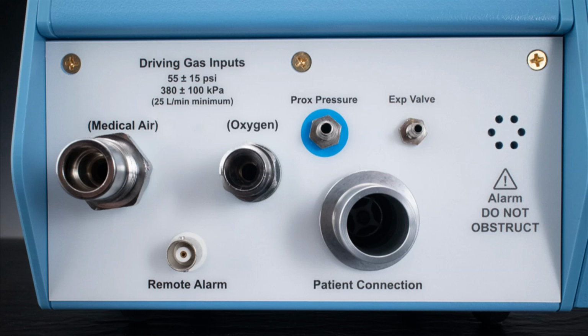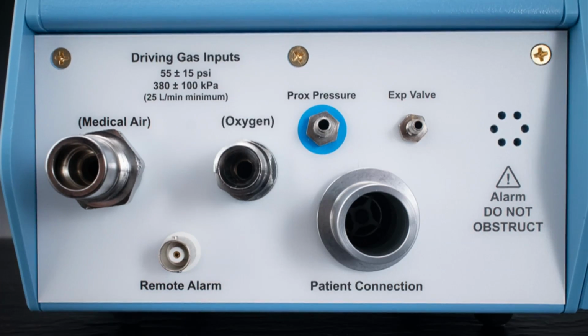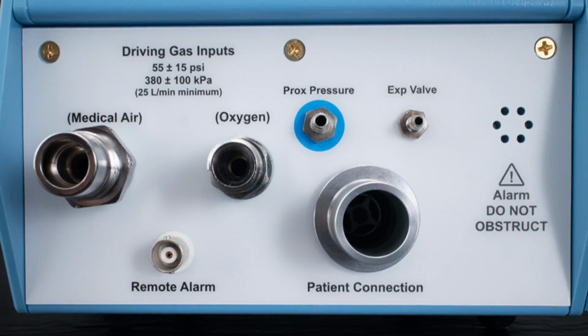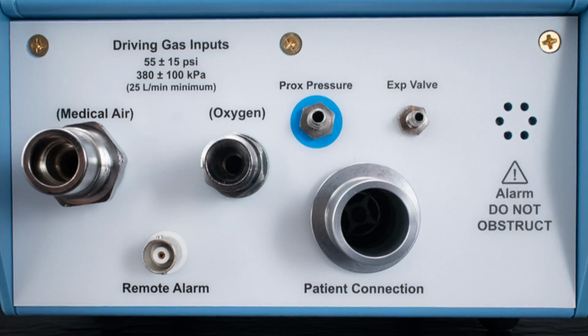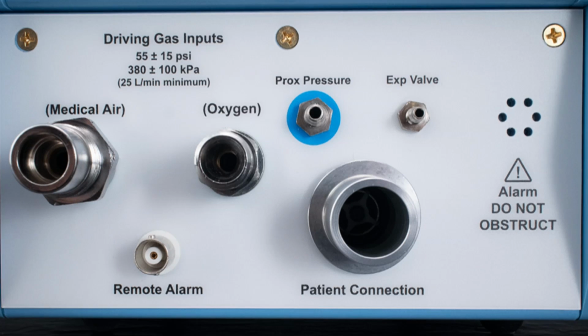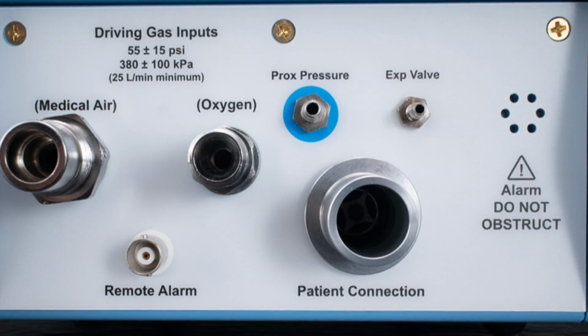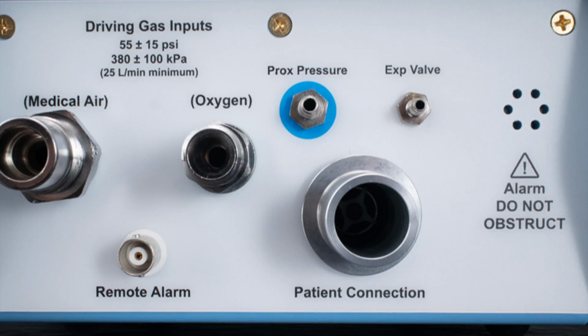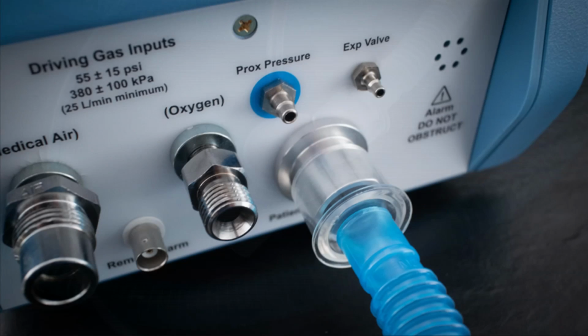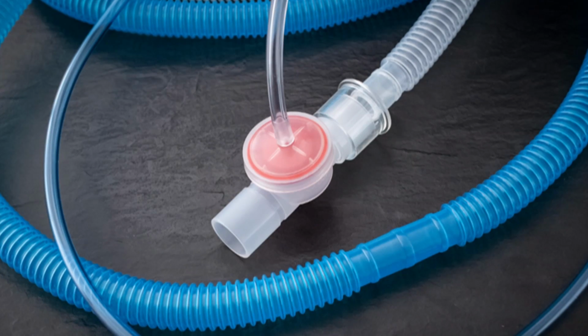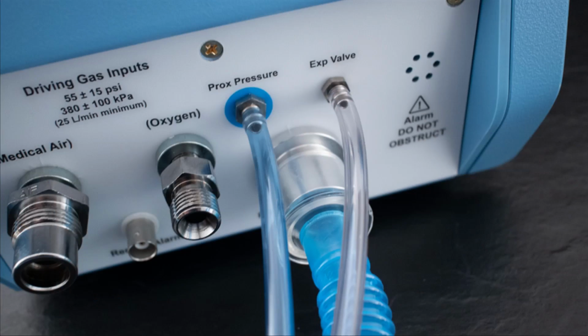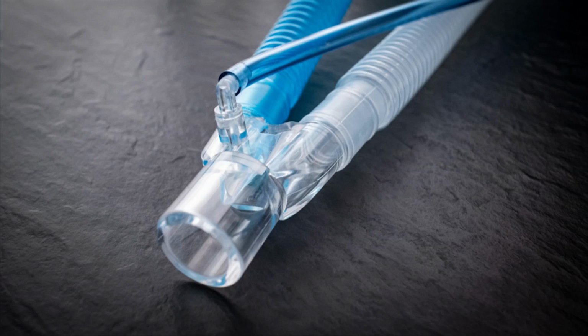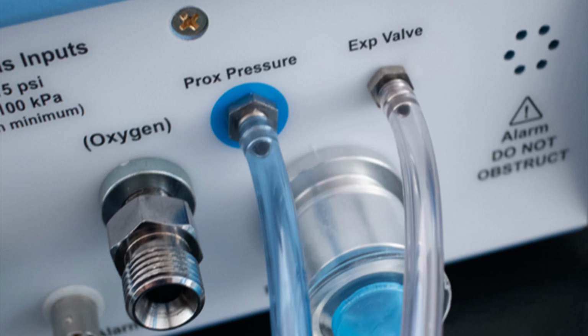Patient connection. To the right of the gas input connections is the patient connection, with proximal pressure noted as prox pressure, and an expiratory or EXP valve fitting which accommodates the patient breathing circuit. The patient circuit is a dual limb system. The inspiratory limb of the patient circuit is attached to the patient connection port with a 22 mm connector. The small tubing, 3 mm, connects the expiratory valve to the expiratory valve barb connection. The small blue tubing, 4 mm, connects the proximal patient port of the circuit to the blue proximal pressure barb connection.